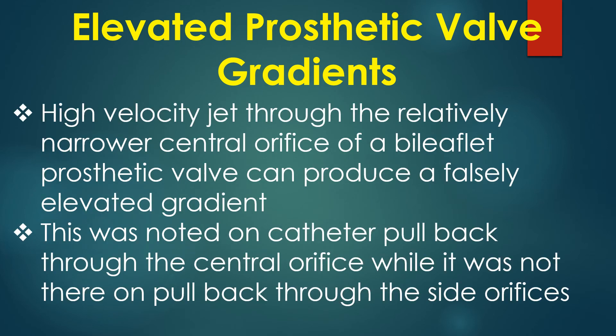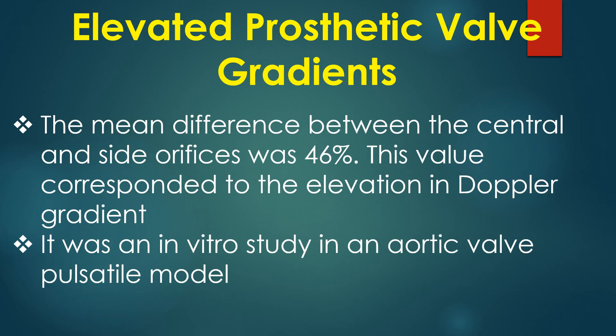A high velocity jet through the relatively narrower central orifice of a bileaflet prosthetic valve can produce a falsely elevated gradient. This was noted on catheter pullback through the central orifice but was not present on pullback through the side orifices. The mean difference between the central and side orifices was 46%, which corresponded to the elevation in Doppler gradient. This was demonstrated in an in vitro study using an aortic valve pulsatile model.